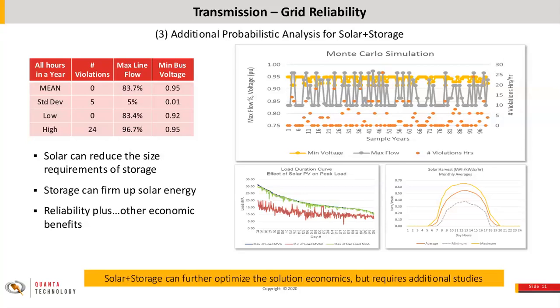We looked at line overloads and minimum bus voltages across the system, the mean, low, and high values, trying to optimize the relative size of storage versus solar. We found that solar can help reduce the megawatt-hour requirements of storage even for reliability purposes, but it requires a lot of analysis to ensure requirements are still met.